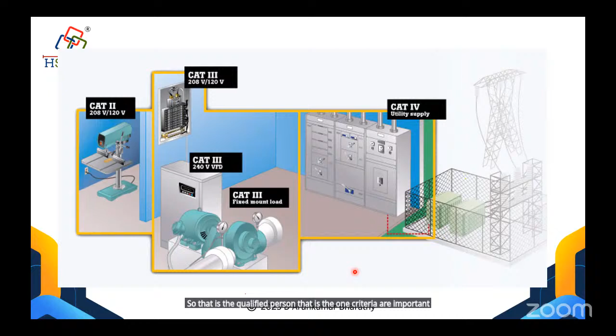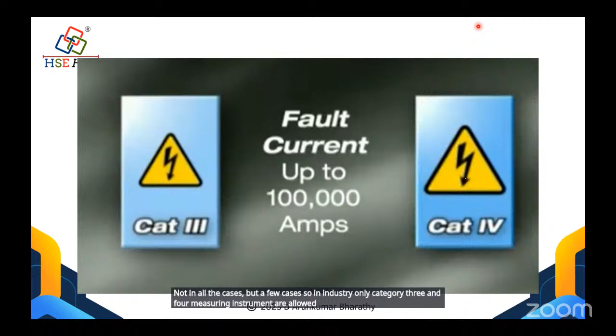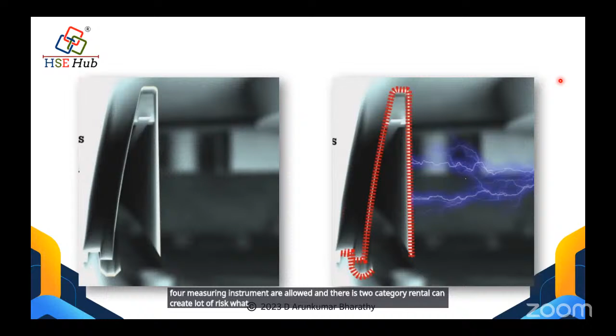And in industry, normally category 3 and 4 will come. That's called power circuit measurement. During power circuit measurement, the estimated fault current may go up to 1 lakh ampere. Not in all cases, but in a few cases. So in industry, only category 3 and 4 measuring instruments are allowed. Otherwise, category 2 and others can create a lot of risk. What is the specialty in the category rating?